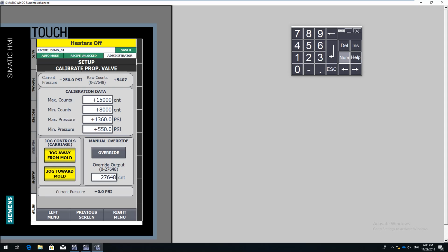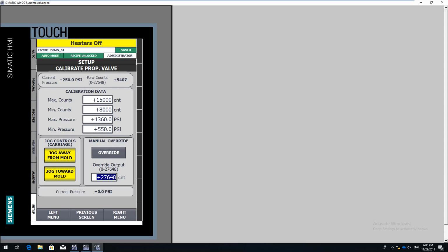So what we're actually doing at this point is we're going to send a 10 volt signal out to the proportional valve. In other words, open up as wide as you possibly can. And I'll turn on the override, so override has to be on. So at this point, I am sending out a raw count of that. If I turn off override, you'll see it go back down to some lower number. So with the override on, we're sending out 10 volts.